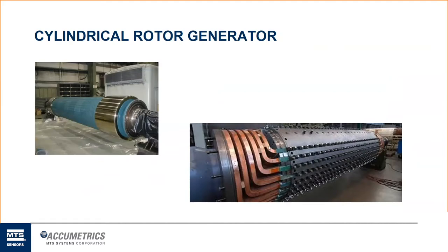They're insulated from themselves with thin layers of insulation. And then they're also isolated from the metal of the rotor itself with fiberglass insulation pieces inside of these grooves. So the issue of a ground fault is you don't want there to be any current flow between the high voltage, high amperage flow of electricity in these bus bars and the metal of the machine itself, the forging of the rotor. If that happens, that can be very bad.